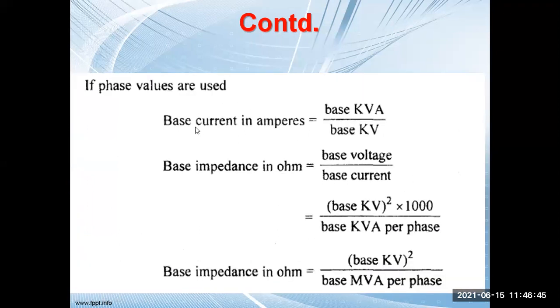Now if you are dealing with the phase values, what will happen? Base current will be base kVA by base kV. The base impedance will be base voltage by base current, since voltage by current is your impedance. So base voltage is base kV square, and base current, we have substituted here, is base kVA by base kV. This base kV comes in the numerator, and into 1000. Now why does this 1000 come in?